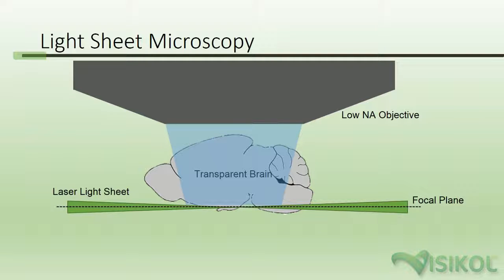The way a light sheet microscope works is by switching from an inverted or upright diffuse light source to a laser light source that is mounted orthogonally to the objective. Using cylindrical shaping lenses, the laser light sheet is transformed into an ultra-thin sheet of light that is, for example, 10 millimeters wide by 5 microns thick. Instead of illuminating an entire depth of the tissue, this approach only illuminates an ultra-thin sheet of the cleared and fluorescently labeled tissue that is in the same plane as the imaging objective's focal plane.